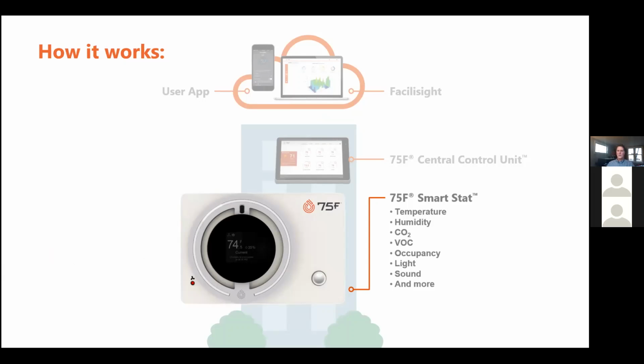One of them is geared towards being a thermostat for any sort of dual or single set point device. This stat is what you'd put on a water source heat pump, a 2-pipe or 4-pipe fan coil unit, a split system, an RTU, unit heater, baseboard radiators—all those devices in the terminal equipment list that can be controlled with a thermostat. We'd use a single device for all of those. The sequences of operation are different—a 2-pipe fan coil operates differently than a rooftop, a package rooftop with heating and cooling—it's just not the same profile.